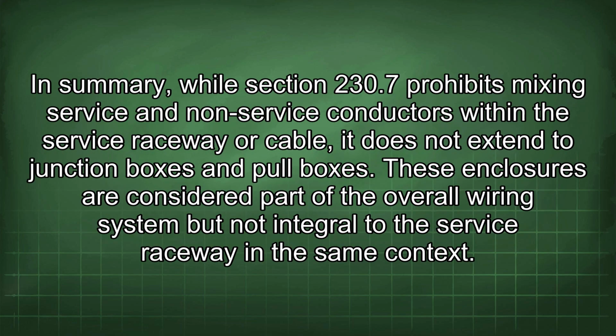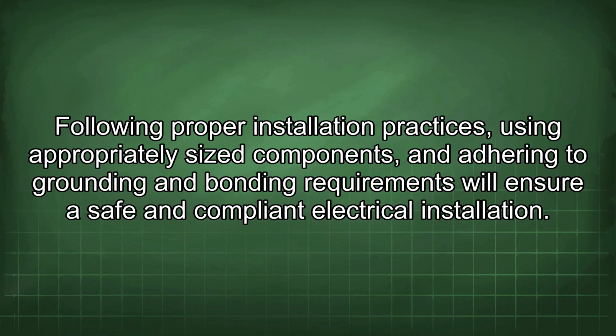In summary, while Section 230.7 prohibits mixing service and non-service conductors within the service raceway or cable, it does not extend to junction boxes and pull boxes. These enclosures are considered part of the overall wiring system but not integral to the service raceway in the same context. Following proper installation practices, using appropriately sized components, and adhering to grounding and bonding requirements will ensure a safe and compliant electrical installation.